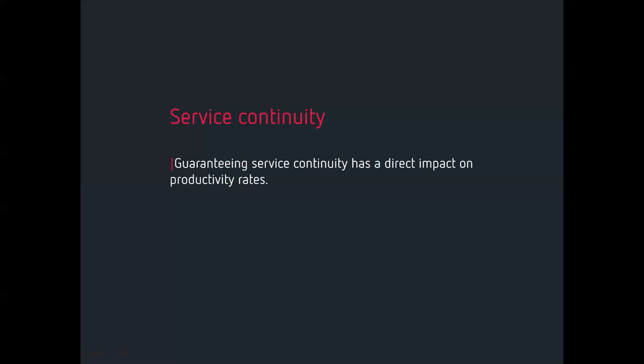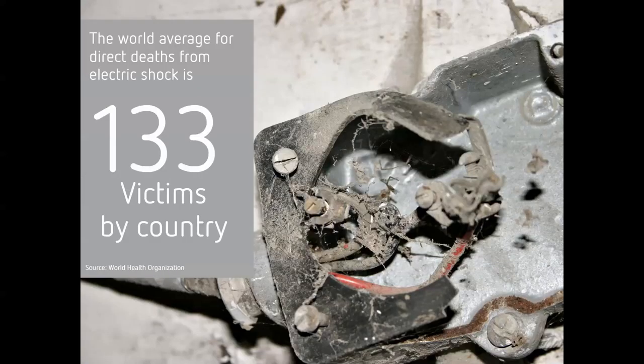We are talking about the fourth point, which is service continuity. Guaranteeing service continuity has a direct impact on productivity rates. It means that if we have a production stop due to a residual current tripping, we will be losing money, so we have to avoid it. Why? Because we need to protect the installations, and we need to protect the people who are working inside the industry.